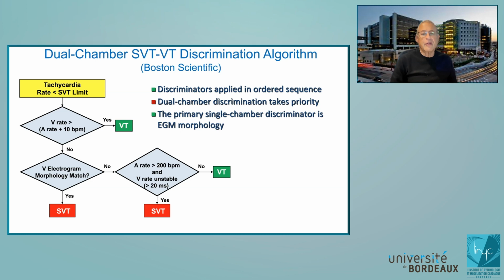A difference, and that's why I put this in red, between the way defibrillators work when they're multi-chamber and single chamber is that when there are dual chamber defibrillators, dual chamber rules take priority, and that's different from clinical ECG rules, and we'll come to why that is later. And then finally, just like we do with surface ECGs, the primary single chamber rule is morphology.